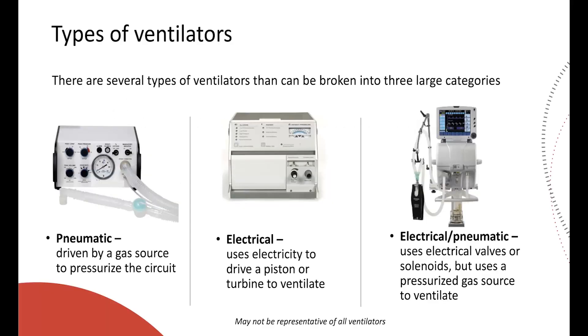First, we're going to go over the types of ventilators that you may see, broken down by what they can actually do. There's a pneumatic ventilator on the left-hand side — this is one powered by a gas source, either from a tank or a 50 psi wall outlet, and it cycles according to the pressure and pneumatics built within it. These are fairly simple devices, often used in disaster situations and on transport.